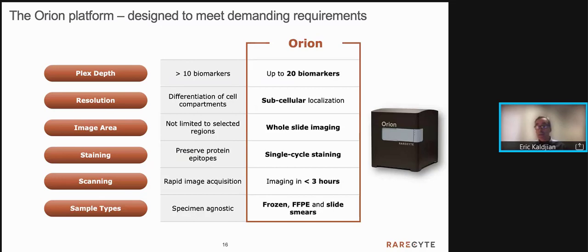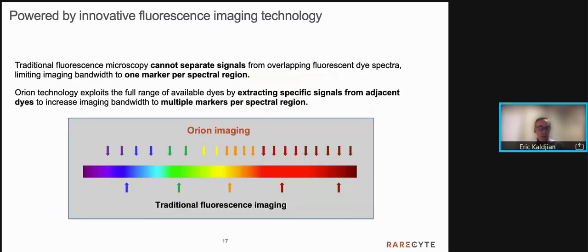We have designed Orion with these attributes in mind. The plex depth for Orion is up to 20 biomarkers. Its resolution is subcellular. It performs whole slide imaging. We use a single-cycle staining process and a single-step scanning process, which is less than three hours for the slide — and could be considerably less depending on the size of the tissue section. And finally, it is sample-type agnostic. What we will be showing here in this seminar is formalin-fixed paraffin-embedded tissues. Traditional fluorescence imaging uses a single dye in each spectral region of the light spectrum, which generally allows for five or six markers to be viewed at a time.